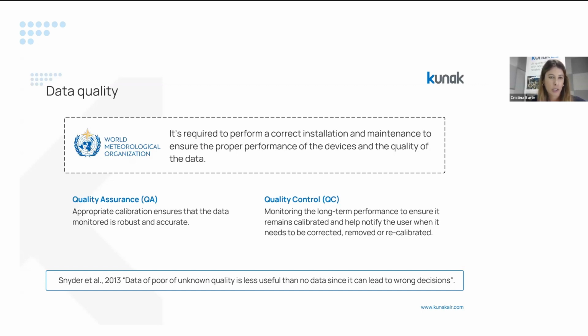Towards that, we find two different methods. First, quality assurance, which is the appropriate calibration that ensures the data monitored is robust and accurate. Then quality control, which means monitoring the long-term performance to ensure it remains calibrated, and helps notify the user when it needs to be corrected, removed, or recalibrated.